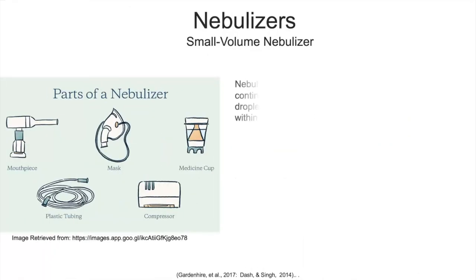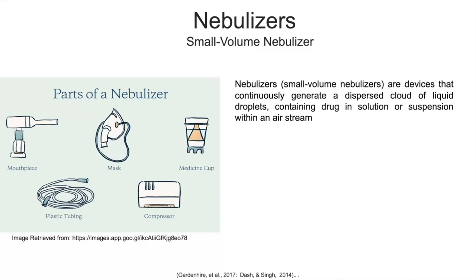Nebulizers, also referred to as small volume nebulizers, are instruments that produce a scattered mist of liquid droplets typically containing medicinal solutions or suspensions within an airflow. They're usually operated by compressed air or oxygen, and a compressor — an electrically powered mechanism — is also involved in this sort of system.